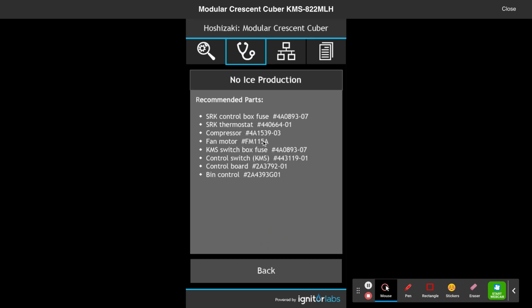Here are the parts for those common issues. When the fan motor goes out, the unit will start up, the compressor will start to run, the pressure will build up when the fan motor is seized up and not turning. Then that pressure builds up, and they have a high pressure cutoff switch that will shut the unit down.